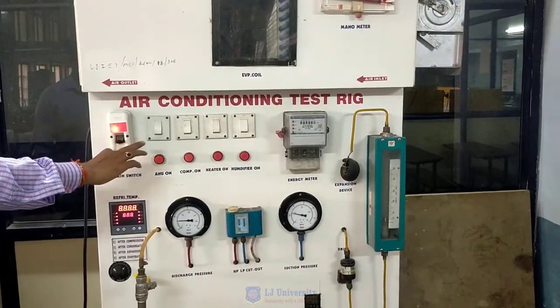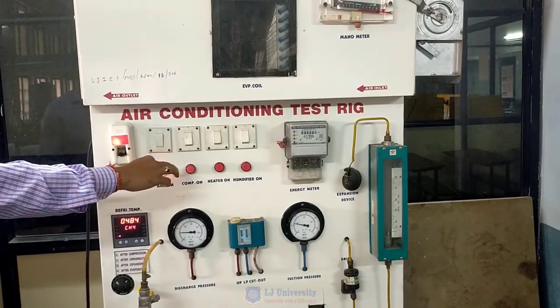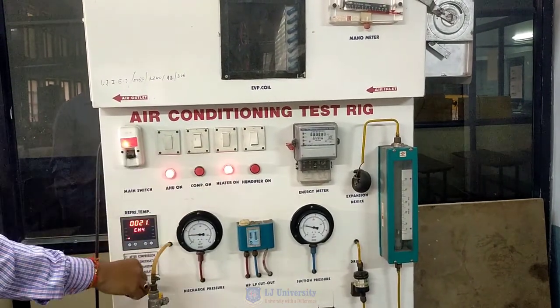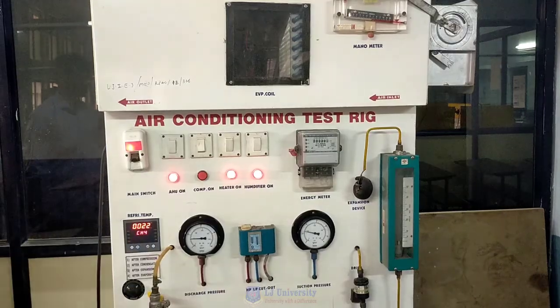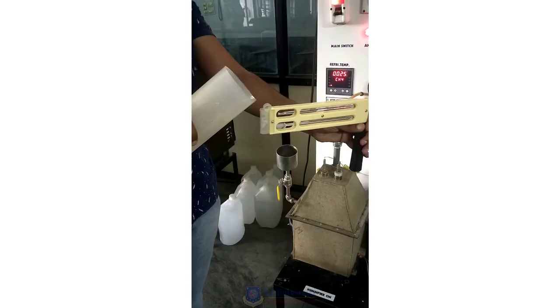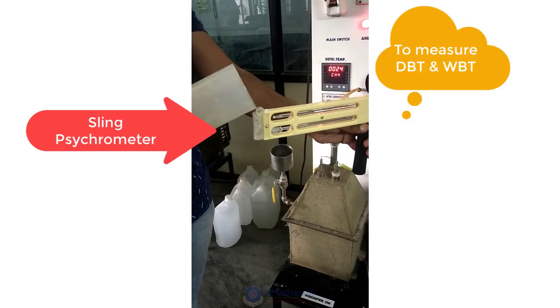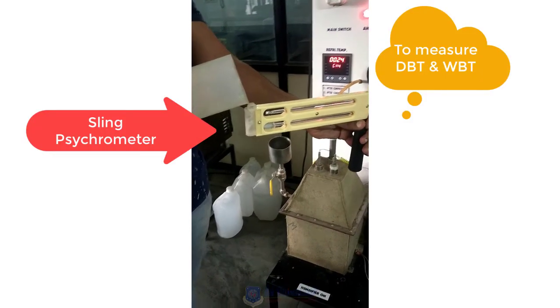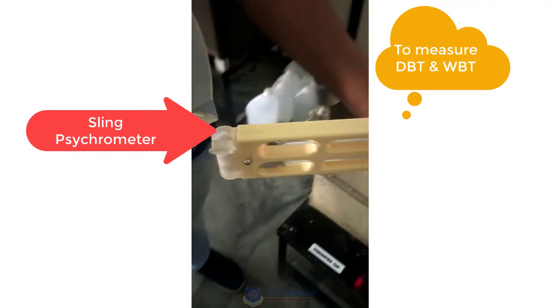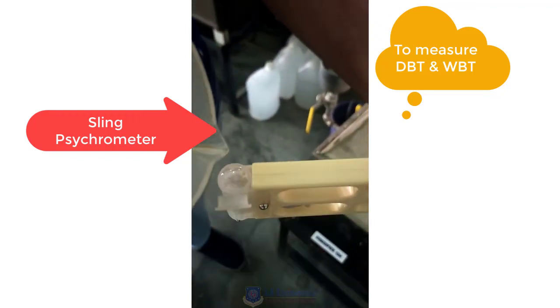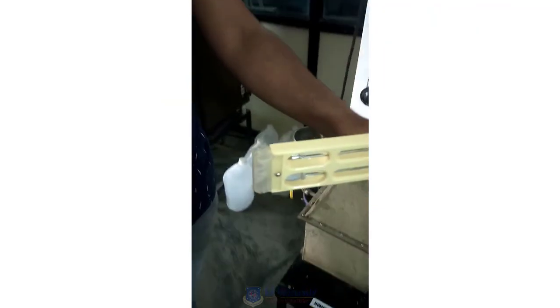So for heating we have to start the air handling unit as well as the heater of the evaporator as well as the humidifier heater. Now after some time we can take readings of the dry bulb temperature, DBT, and wet bulb temperature, WBT, with the help of a sling psychrometer. This is a sling psychrometer. By using this psychrometer we can measure WBT and DBT of the inlet condition as well as the outlet condition.